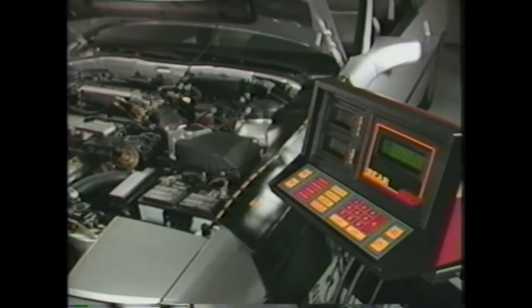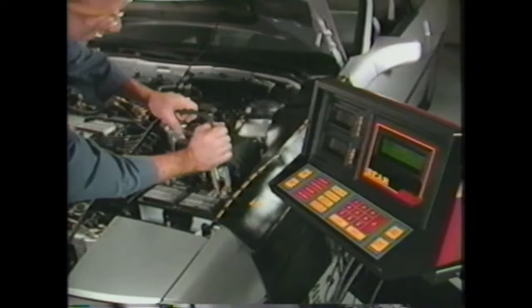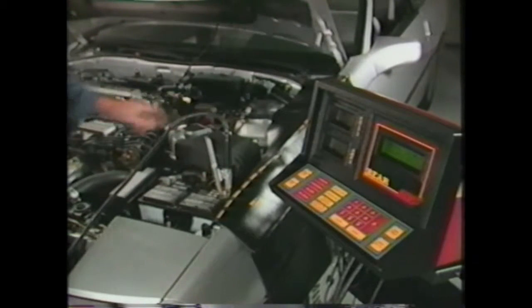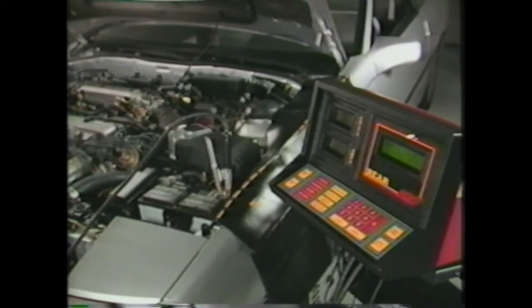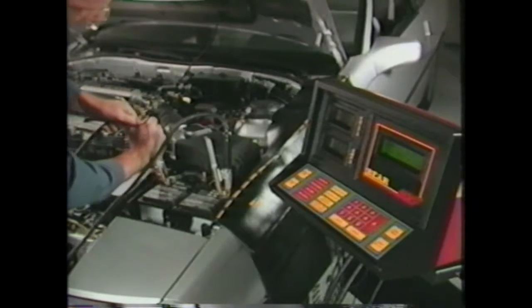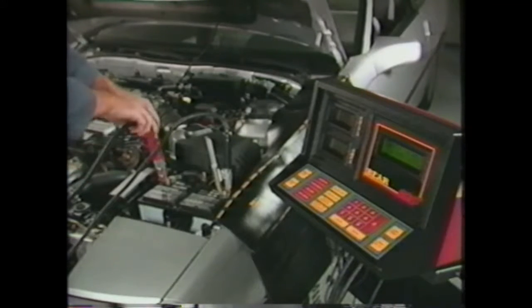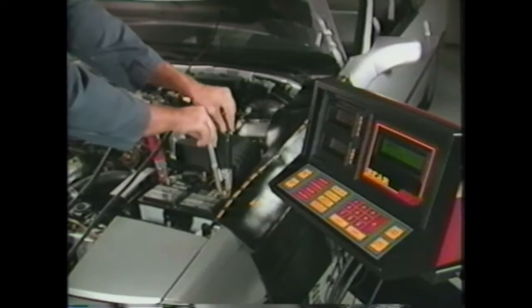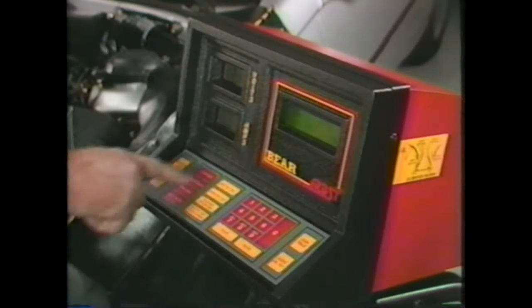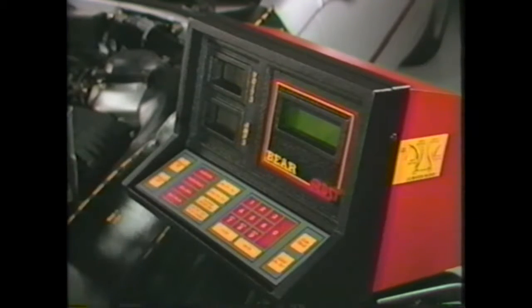First, connect the tester's heavy load leads to the battery. Connect the black negative lead to the negative battery terminal. Do not connect it to any other ground. Connect it directly to the terminal. Connect the red positive lead to the positive battery terminal. Make sure both clamps are securely connected. Press the battery test key to start the test procedure.